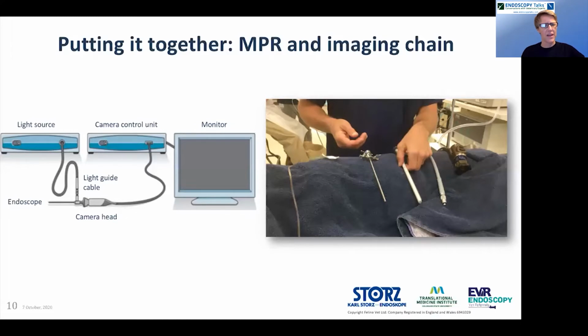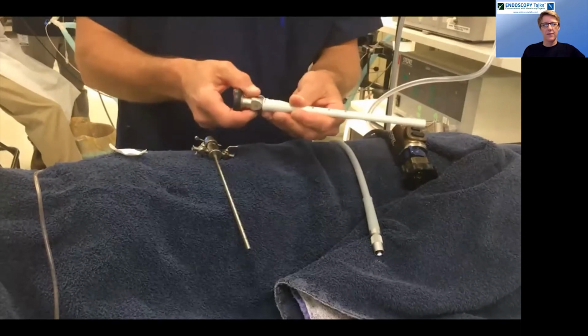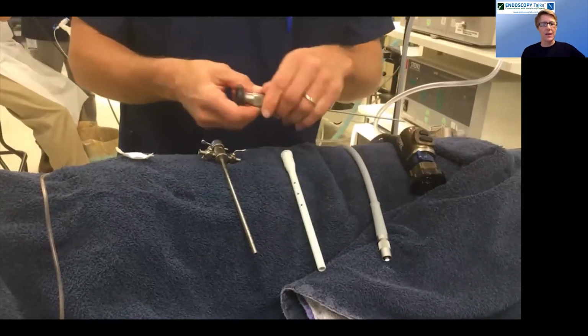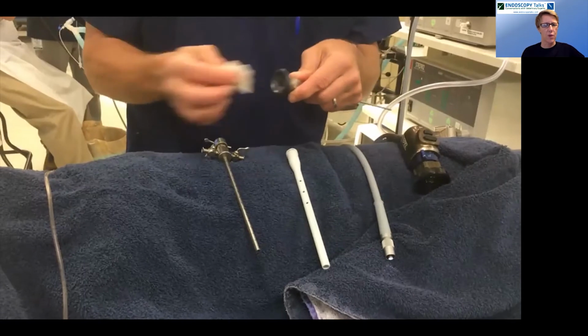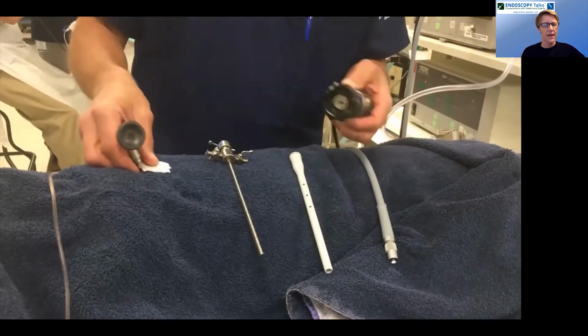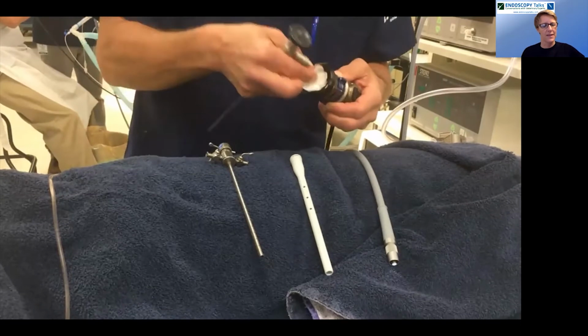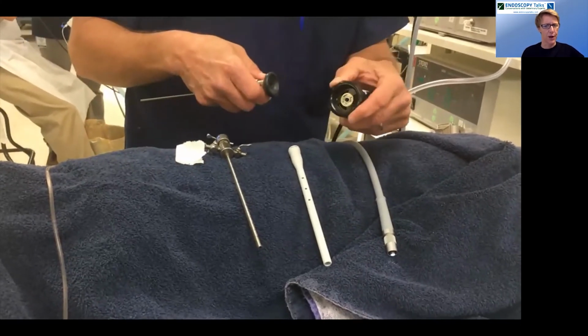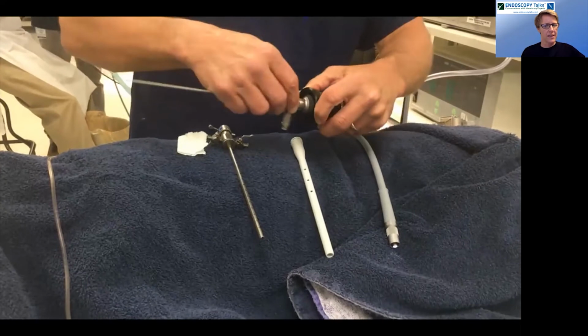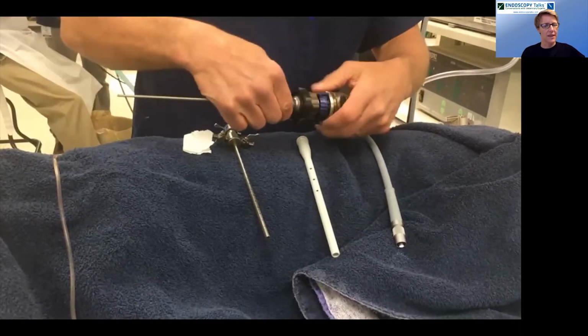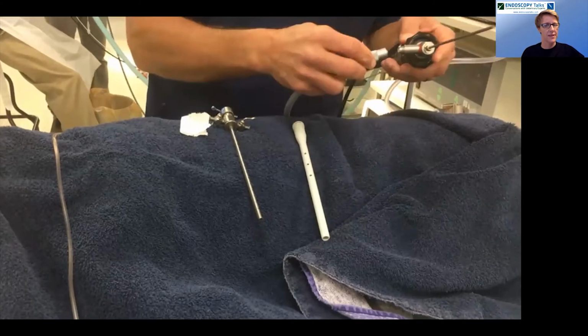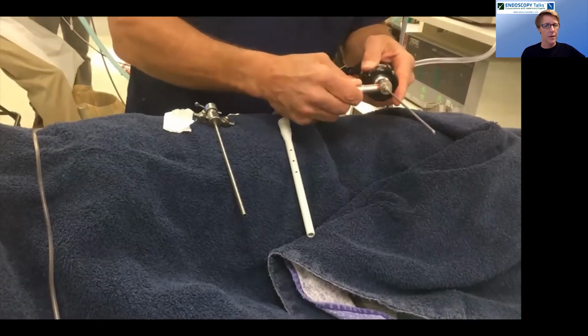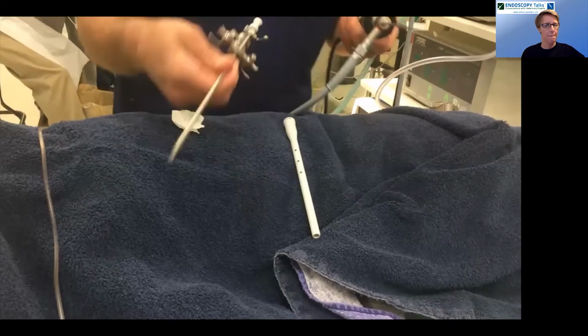And then you also need to have a light guide cable which connects from the light source to the light guide post of the endoscope. This image over on the right, this is a video, and so basically your endoscope will typically be in a protective sheath, and what you want to do is wipe off the oculus of any fingerprints and also from the camera head, because if you have a fingerprint, that can pretty much blur your image. Then what you want to do is take the locking piece on the camera head and make sure that's securely attached to the oculus of the endoscope, and then attach the light guide cable to the base of the endoscope.